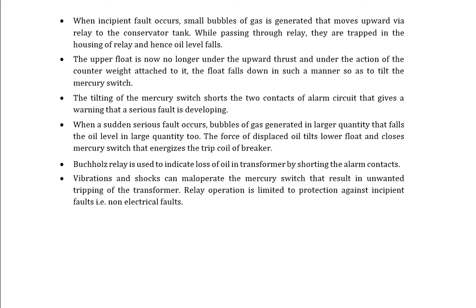Okay, so the Buchholz relay is used to indicate the loss of oil in the transformer by short circuiting the oil alarm contact. Vibration and shocks can maloperate the mercury switch, which results in unwanted tripping of the transformer. So we have to take care about vibration and shocks. Relay operation is limited to protection against incipient faults, non-electrical faults only. Okay, so the relay only operates for incipient or internal faults.